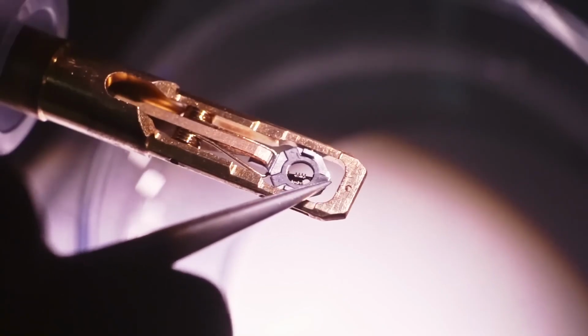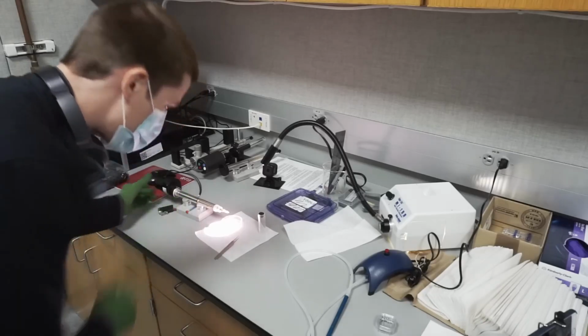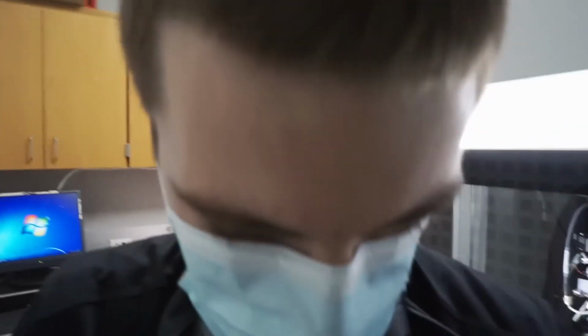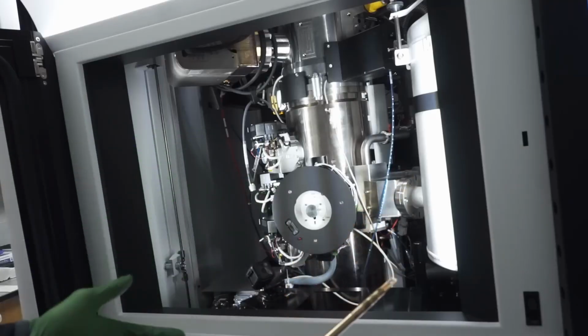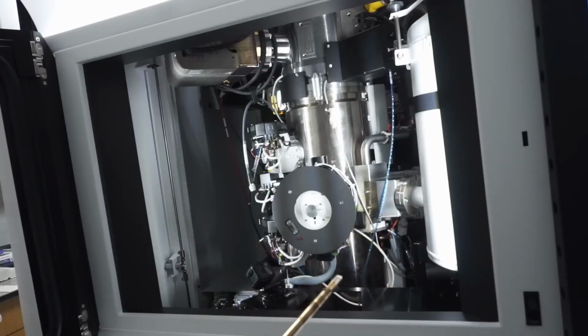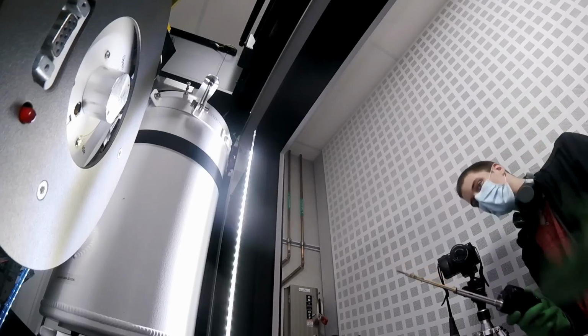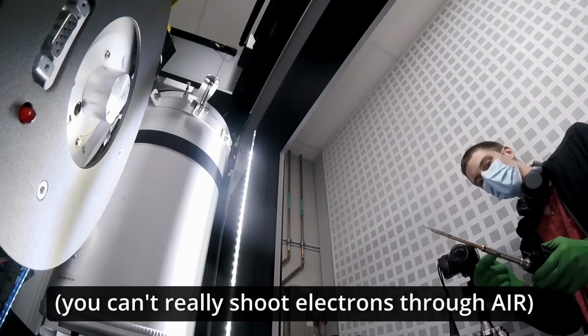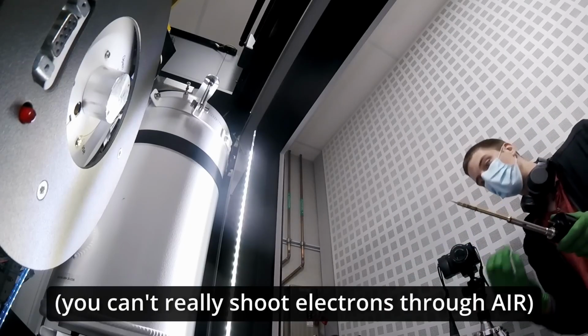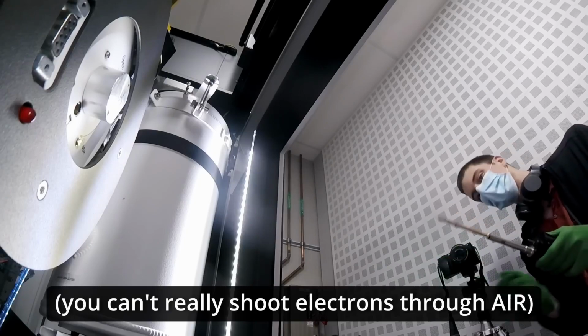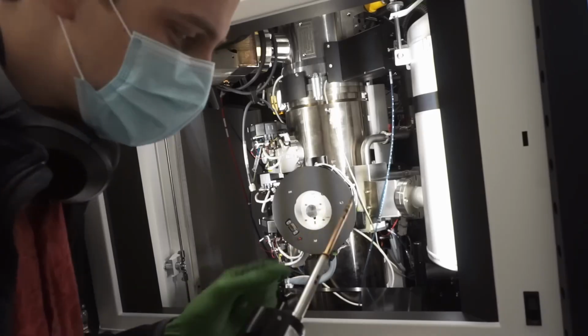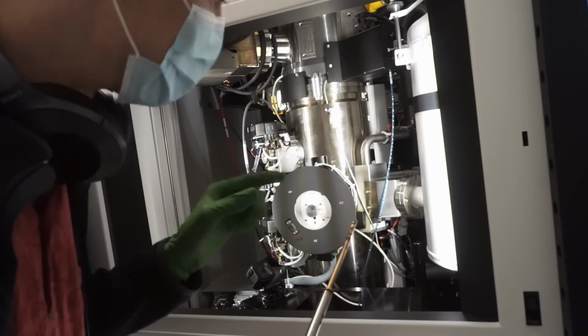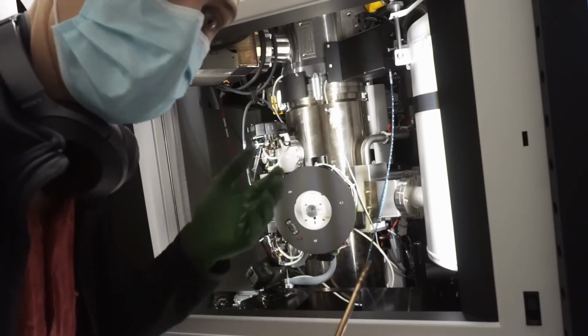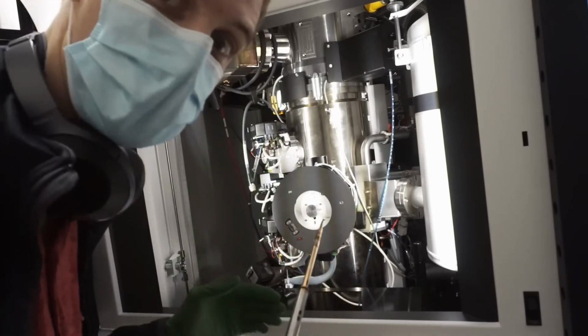So now that the sample is mounted inside of this chuck, if you'll follow me around the corner, in here we have the actual microscope. Like all electron microscopes, the STEM here is basically just a big multi-compartment vacuum chamber, which means that this thing, when I load it into the chamber, needs to be able to stop all of the air from rushing in behind it. When I put this in, it's actually going to create a seal at this O-ring, and then I'm going to have to wait for a few minutes while it pumps out the airlock before I can push it all the way into the microscope.